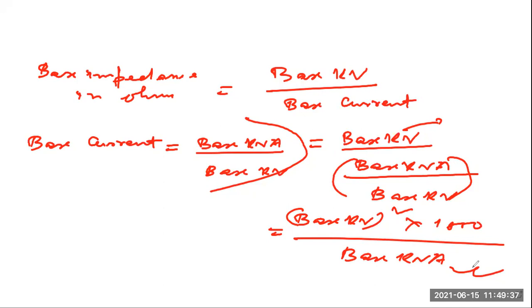So once again: this is base kV by base current. Base current equals base kVA by base kV. So you have substituted here: base kV by (base kVA by base kV). Now here this kilo will cancel, kilo there is no problem. This volt-ampere, if you take it as 1000, and here it is 1000, so you are converting it into your actual unit, meaning the normal unit of volt, current, like that. So this base kV will be in the numerator, that is base kV square into 1000 - we are converting kilo to volt, so 1000, and this will be base kVA. So this is basically the expression when we are dealing with base current.